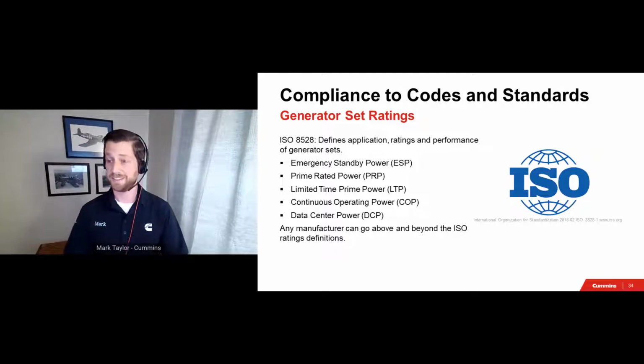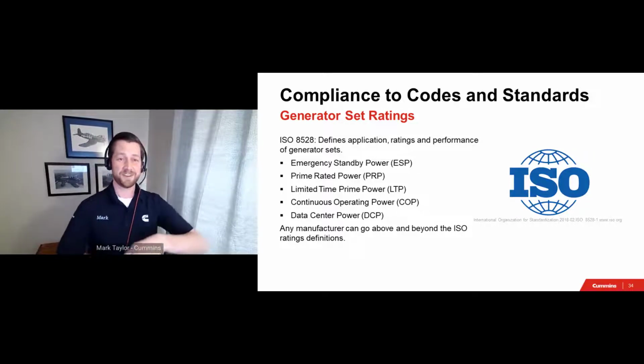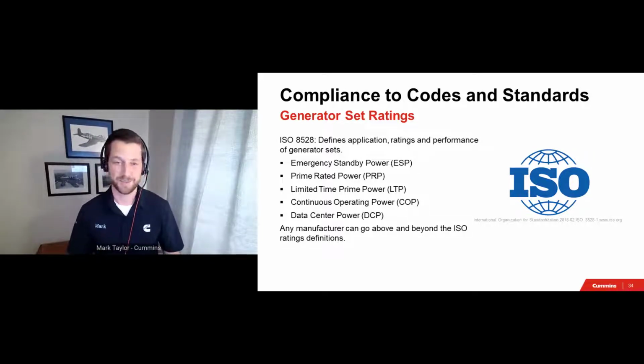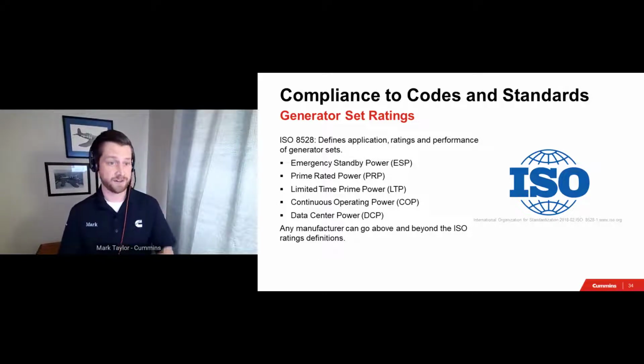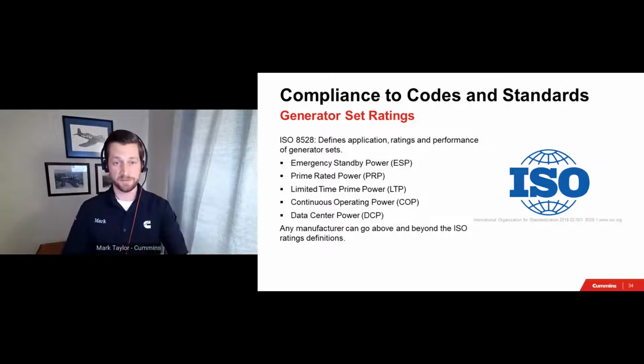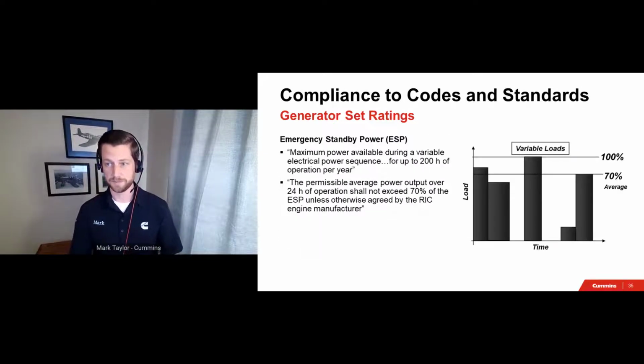The next standard, shifting gears here, the next standard we're going to be covering is ISO 8528. I'm certain it is being called out in your generator set specifications, but usually specs do not go much further than calling out emergency standby power rating. I want to ensure that we level set the expectations of calling out an ISO rating. The first thing to reinforce is that these ratings do not include any fuel type requirements, so it's effectively blind to the selection of fuel used in the generator set, whether it is diesel or gaseous.